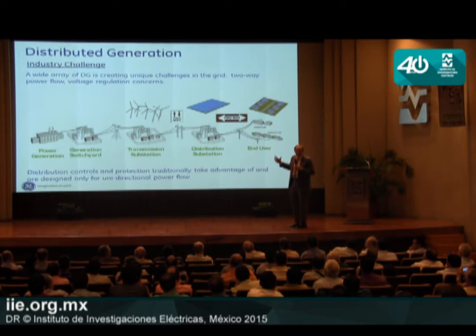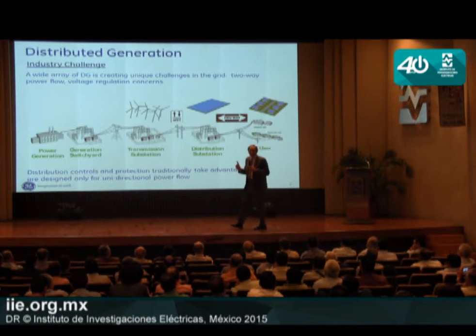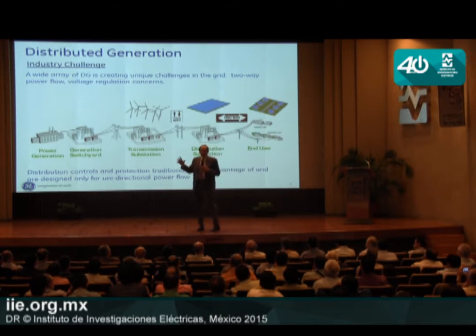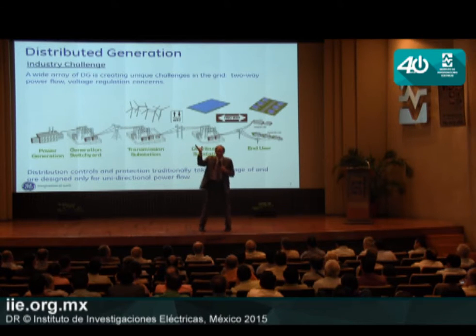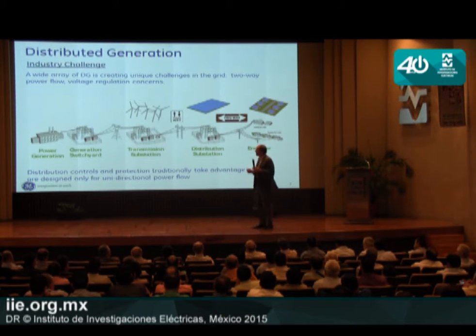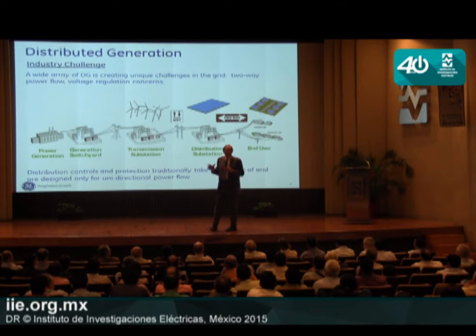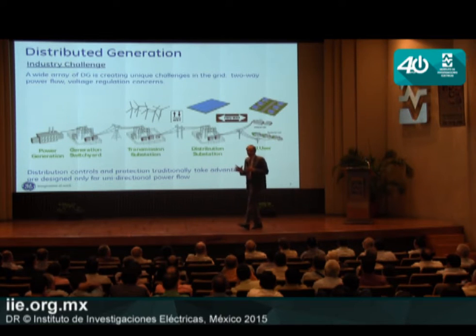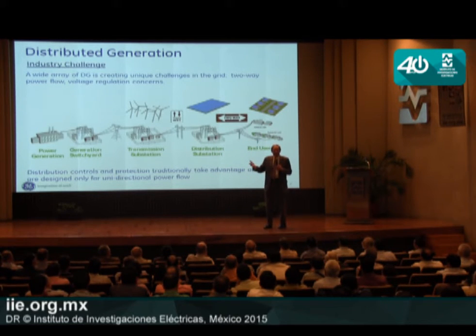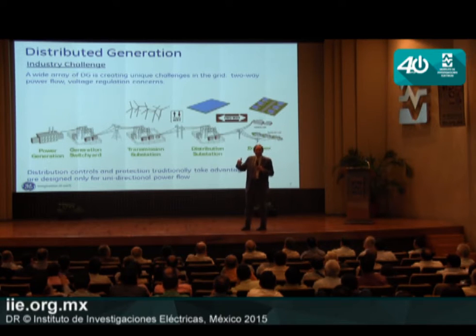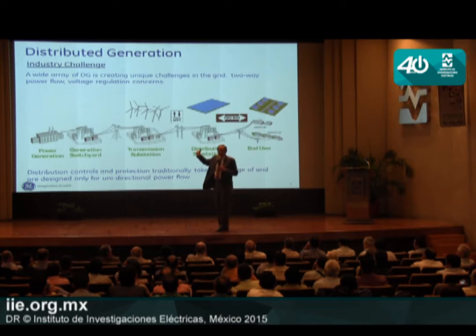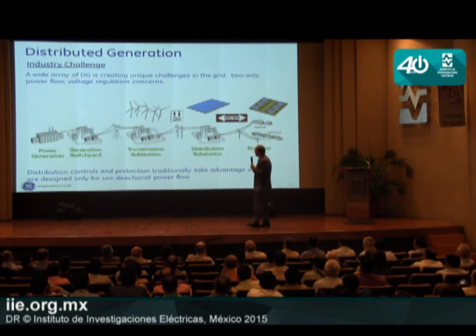What happens with renewables? When we integrate them on the distribution system, now we have electricity flowing in two directions - source to load, plus a contribution from the renewable upstream. So we have two-way flow. What happens with protection? We have to look at protection. What happens with safety? If I go out to work on a line, I used to be able to just open an upstream device and the line would be de-energized. That's not the case now with renewables.